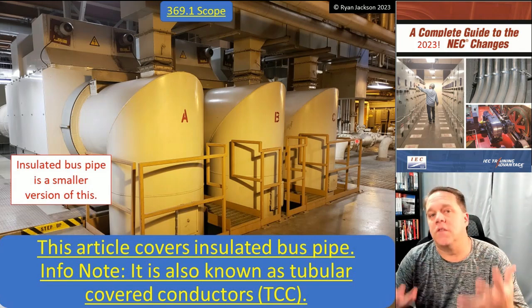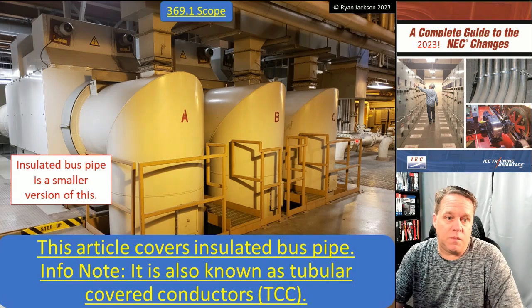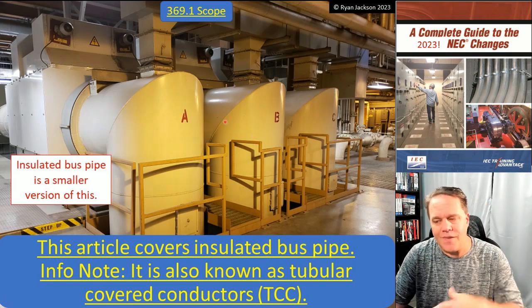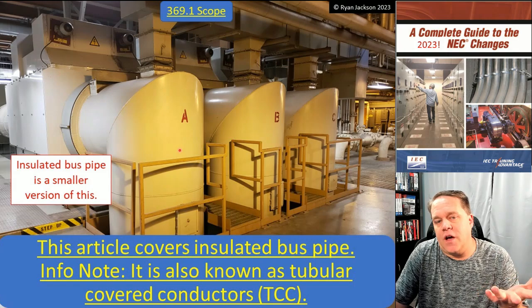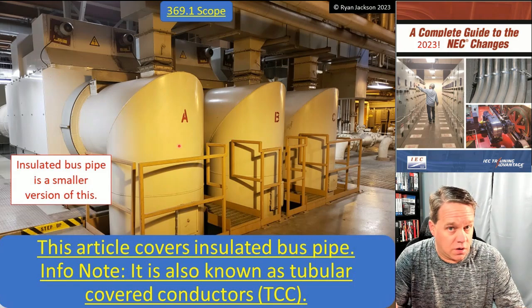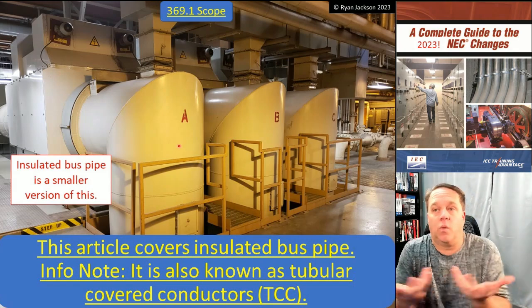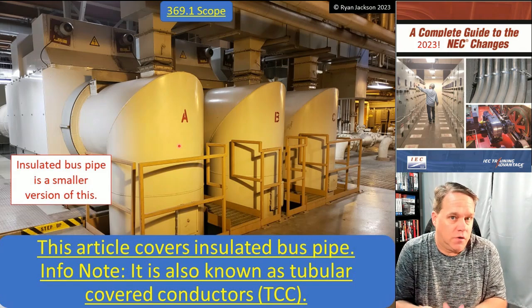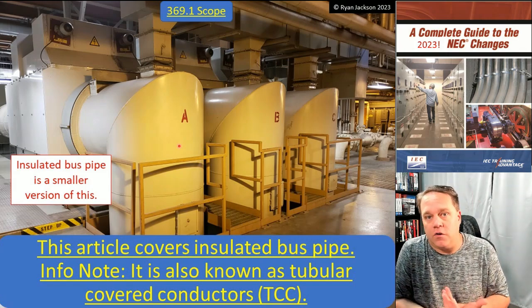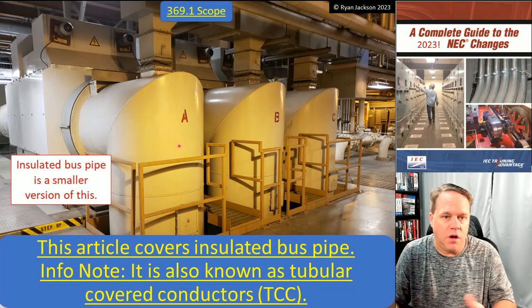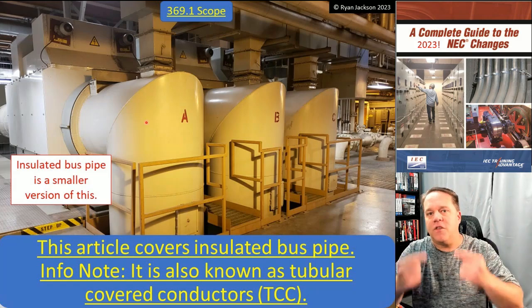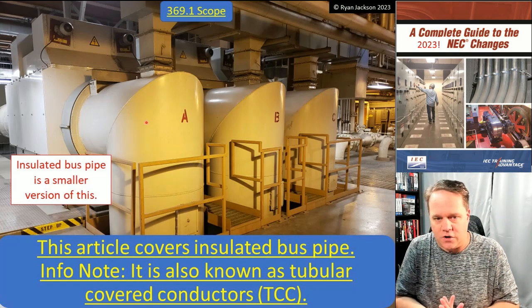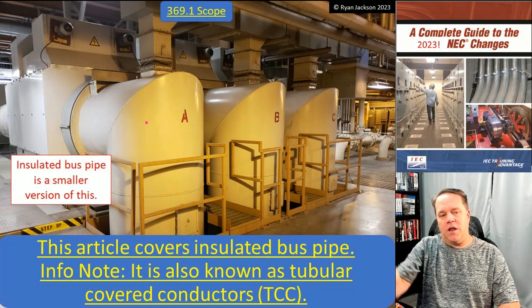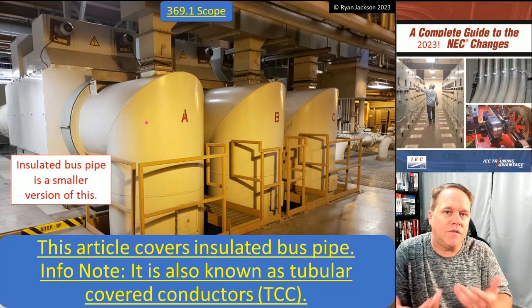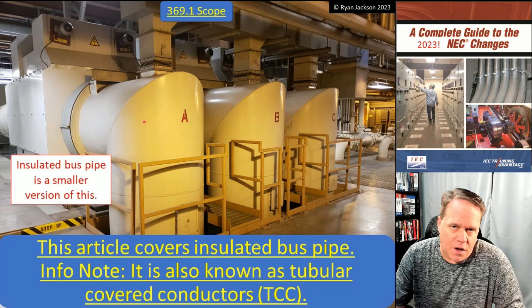One of the things this allows you to do, you can see in the picture, you're not going to be able to move this kind of power with a literal wire. What kind of insulation is good for 26,000 volts? There is none. What size of wire is good for 22,000 amps? There is none. But imagine if this was a cable, a conductor, what would the bending radius be? When you have to change directions, it would be almost impossible.